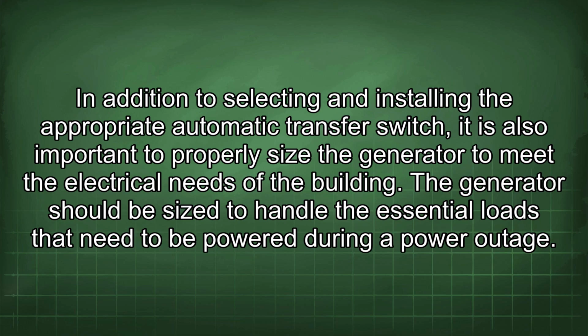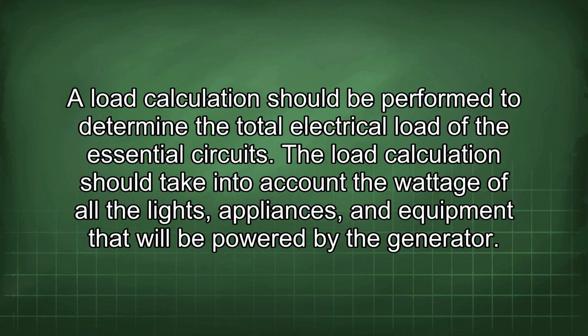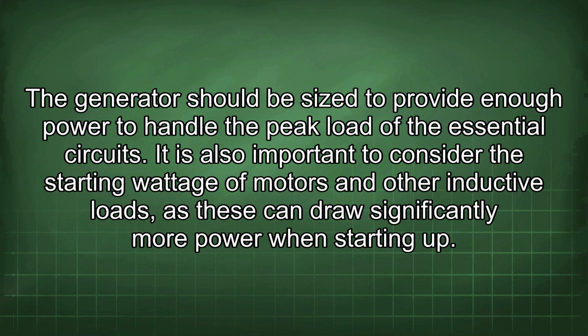In addition to selecting and installing the appropriate automatic transfer switch, it is also important to properly size the generator to meet the electrical needs of the building. The generator should be sized to handle the essential loads that need to be powered during a power outage. A load calculation should be performed to determine the total electrical load of the essential circuits.